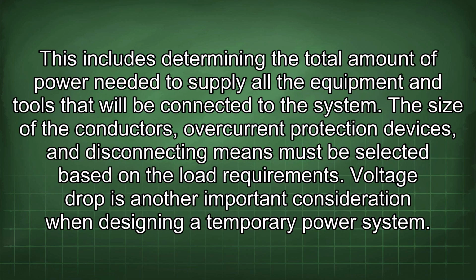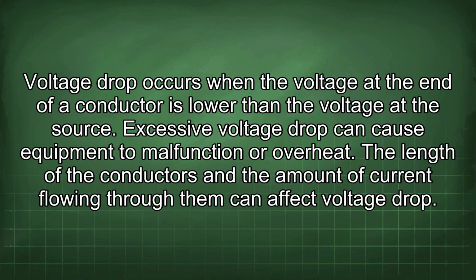This includes determining the total amount of power needed to supply all the equipment and tools that will be connected to the system. The size of the conductors, overcurrent protection devices, and disconnecting means must be selected based on the load requirements. Voltage drop is another important consideration when designing a temporary power system. Voltage drop occurs when the voltage at the end of a conductor is lower than the voltage at the source.